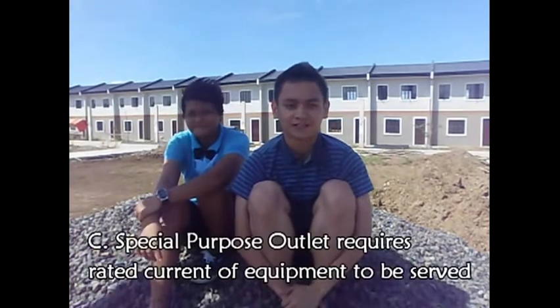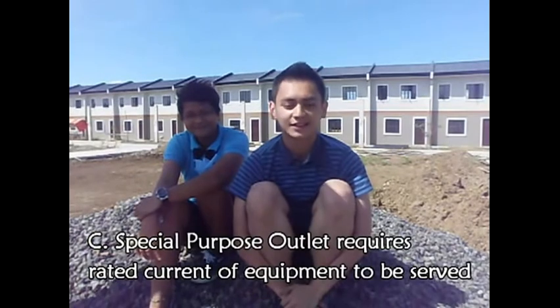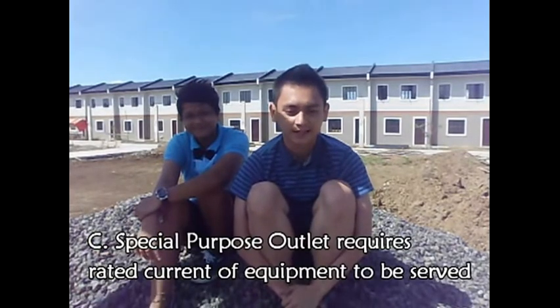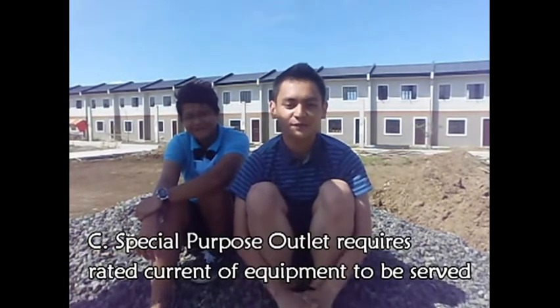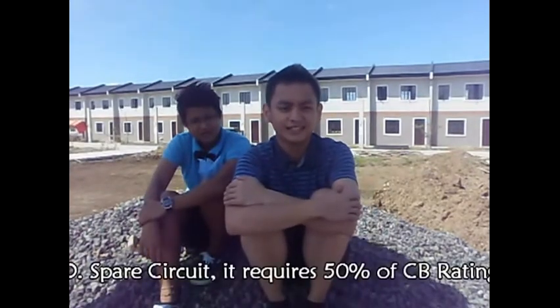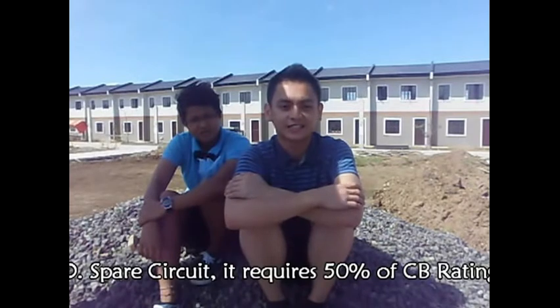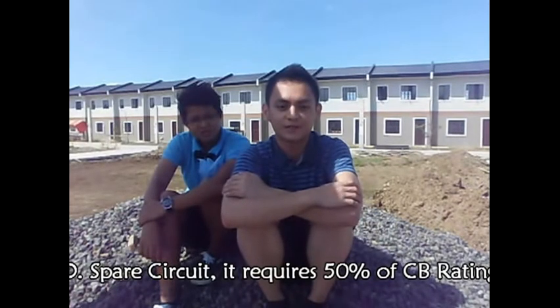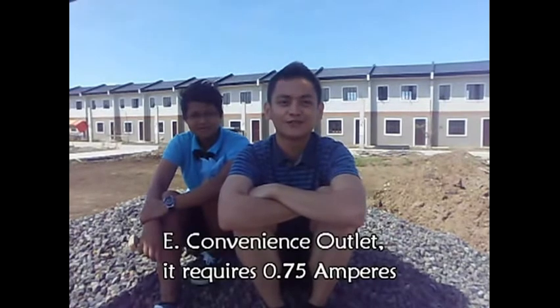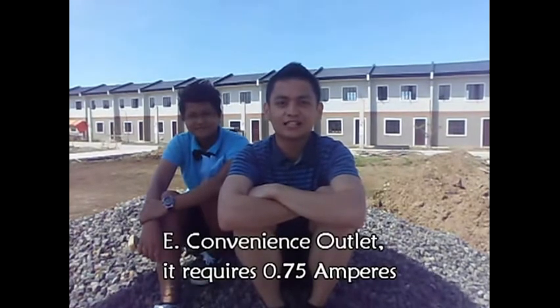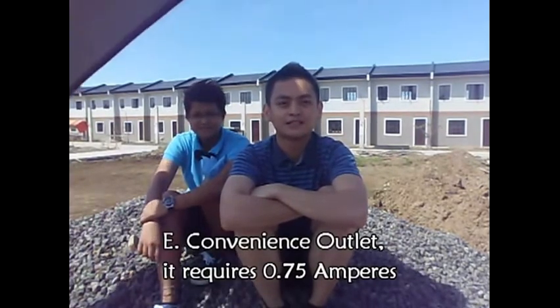Letter C. Special purpose outlet. It requires rated current of equipment to be served. Letter D. Spare circuit. It requires 50% of CB rating. Letter E, convenience outlet. It requires 0.75 amperes.